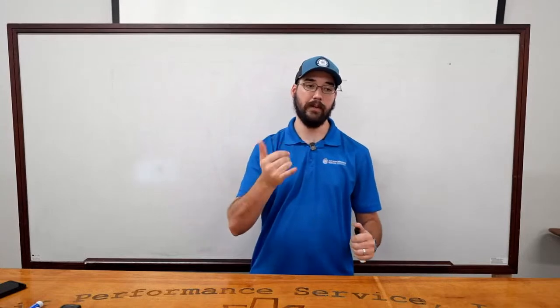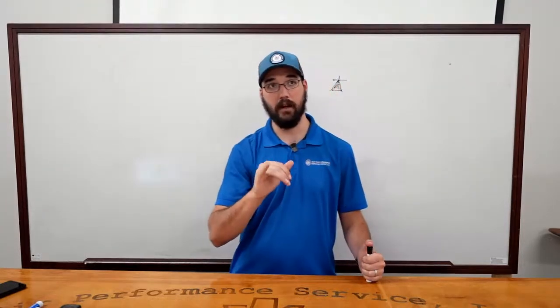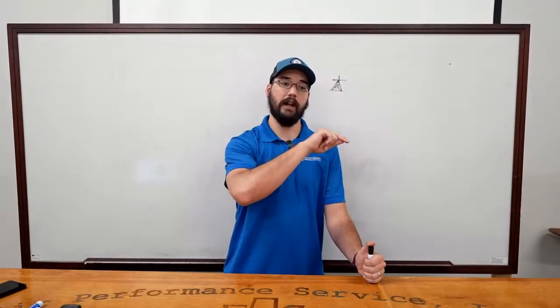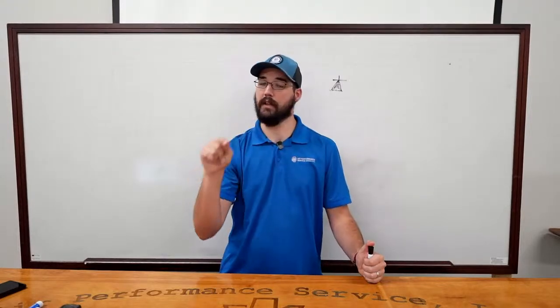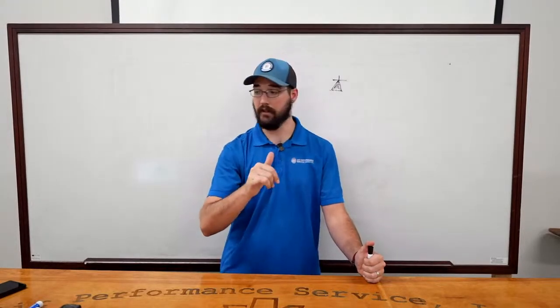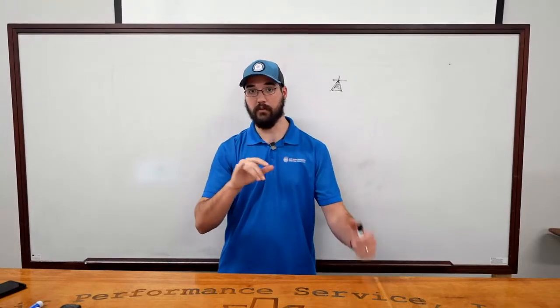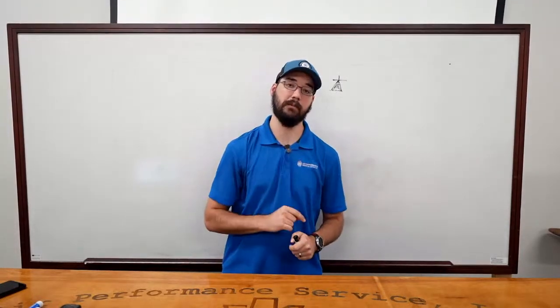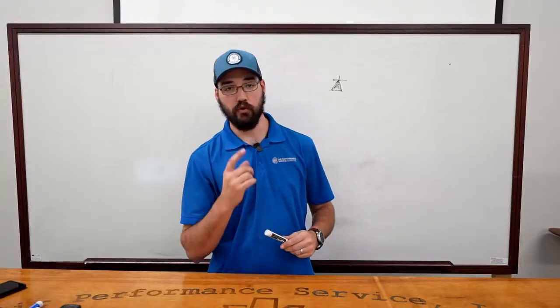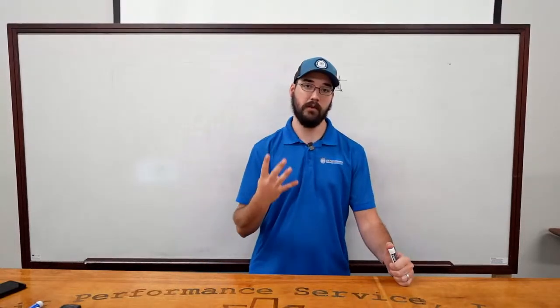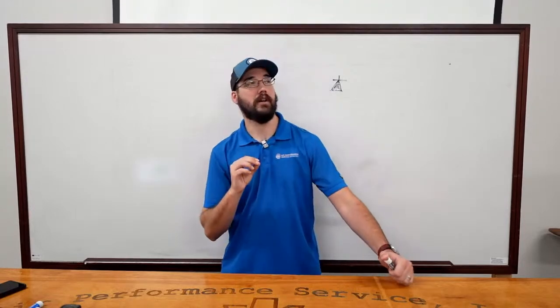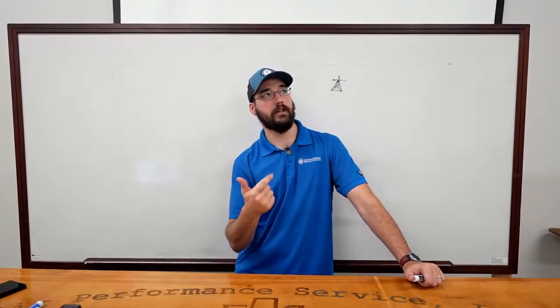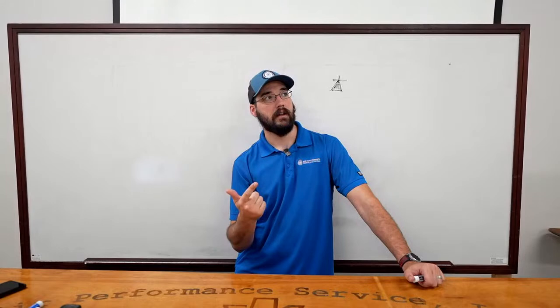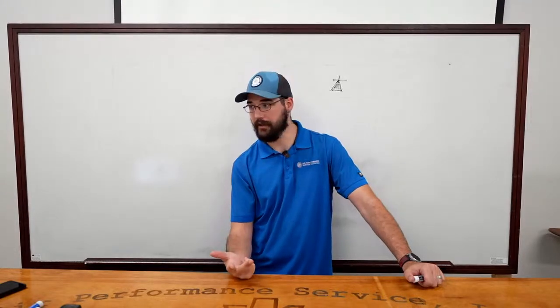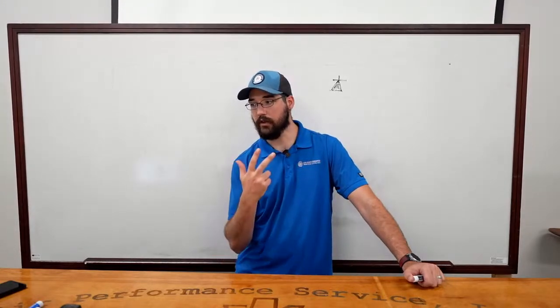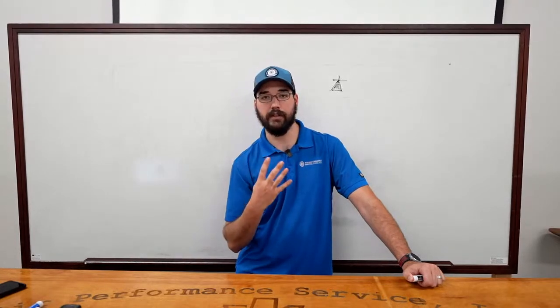And now something else you have to bear in mind is being careful that you're not looking at a heat recovery manual versus a heat pump. Because if I'm not mistaken, they do separate those. Those will be two separate ones, but that also comes back to your model number. So usually it's the first 4 digits of the model. I'm trying to think. I know Mitsubishi, Daikin, and I'm pretty sure LG. You're going to base everything off of those first 4 digits.